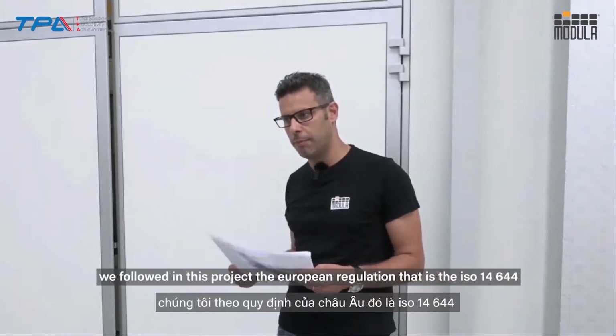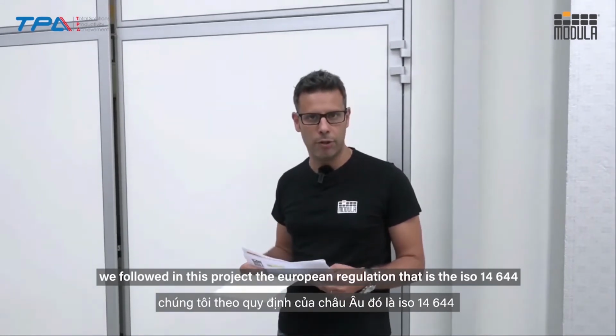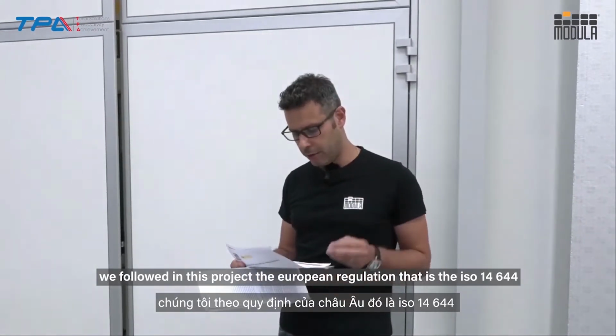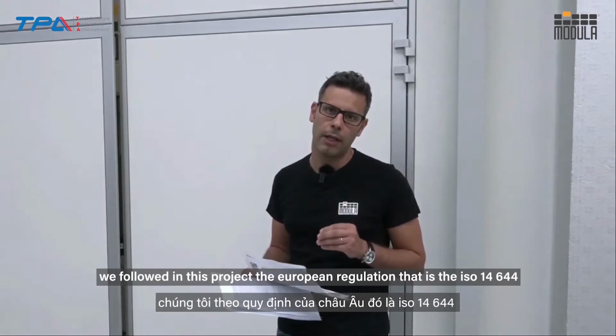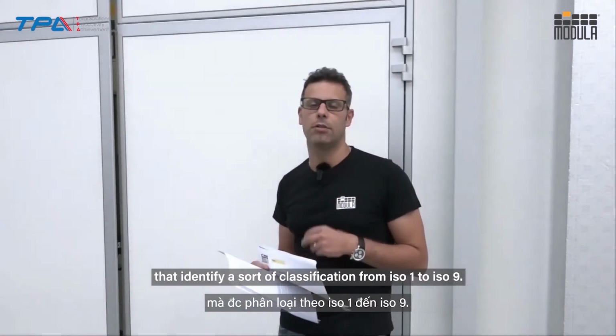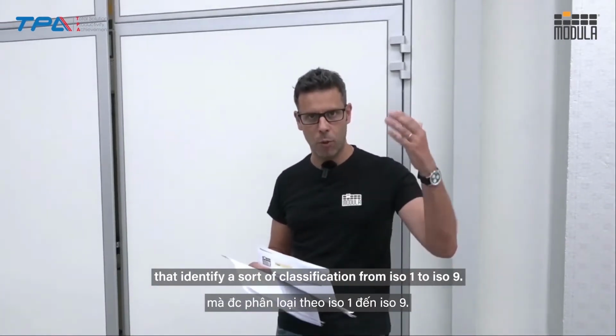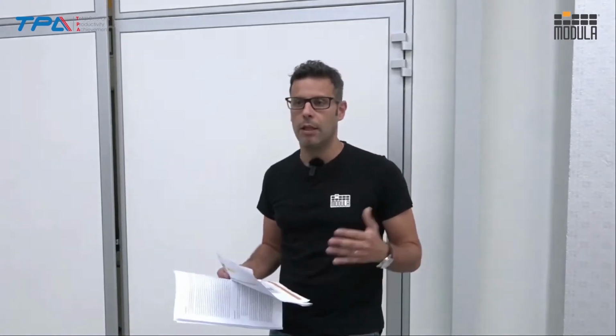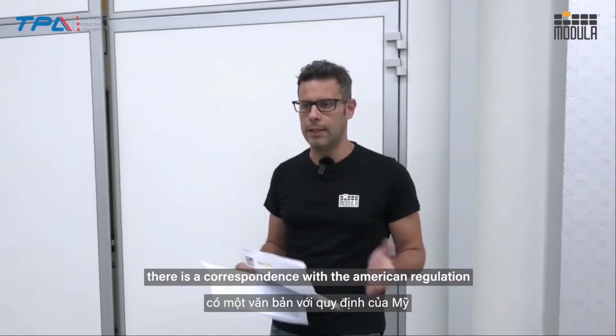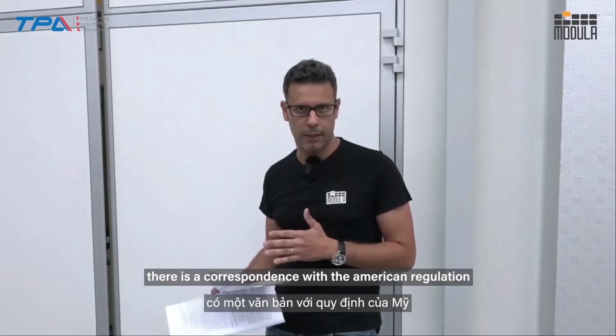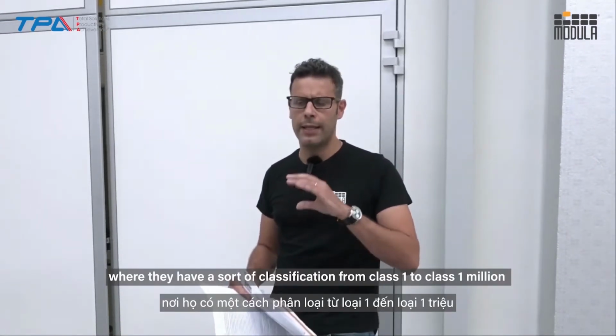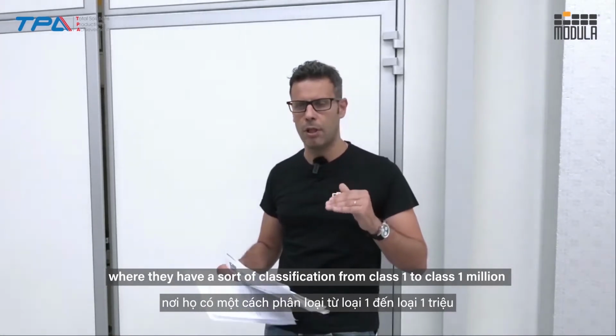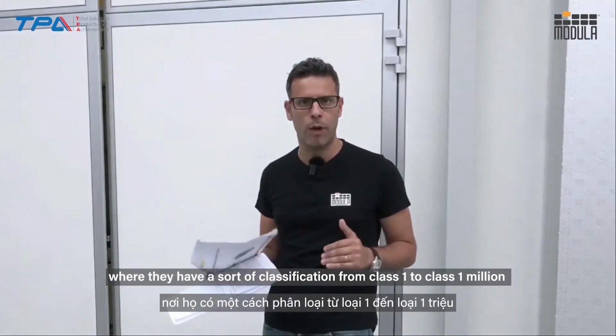We followed in this project the European regulation, that is the ISO 14644, that identifies a classification from ISO 1 to ISO 9. There is a correspondence with the American regulation, where they have a classification from class 1 to class 1 million.